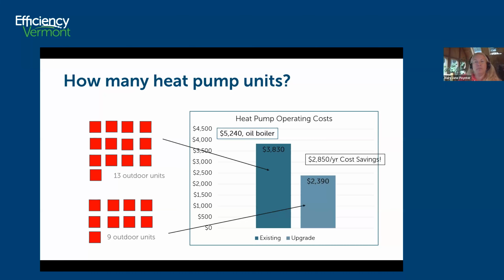So how many heat pumps? I purposely did not look at a VRF system for this building because it's a little bit harder to visualize. I stuck with the 1-to-1 units because people are really used to the 1-to-1 units. And Mary Jane, can you just say what a VRF is? Oh yes, variable refrigerant flow or variable refrigerant volume. That's where you can have one outdoor unit to, I think, as many as 16 indoor heads.